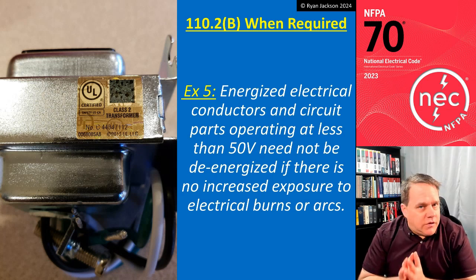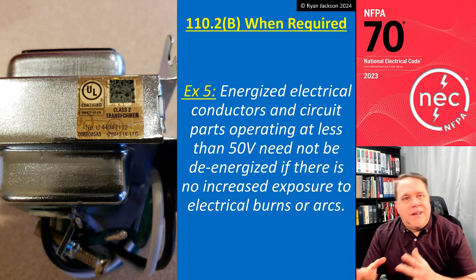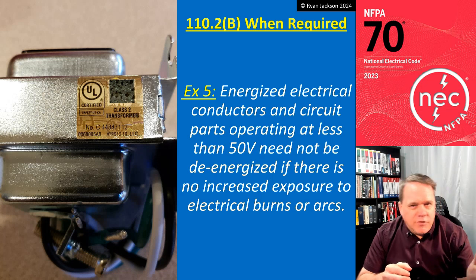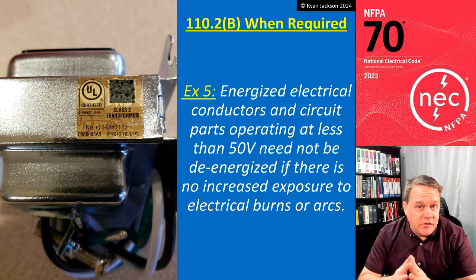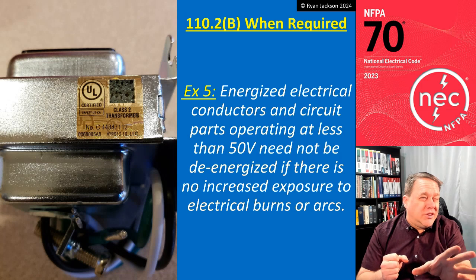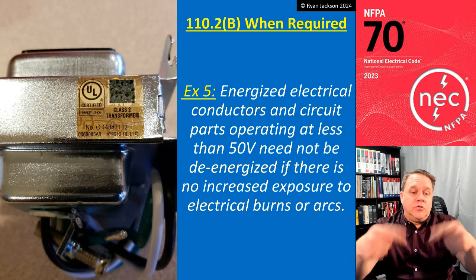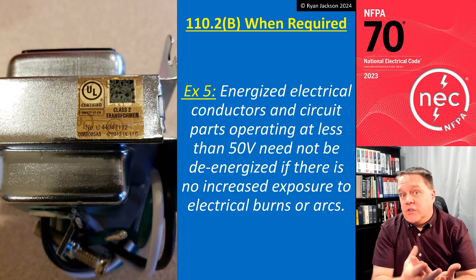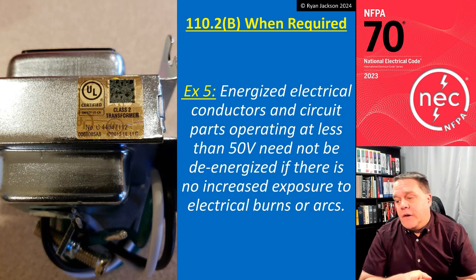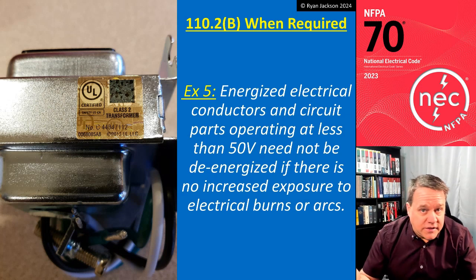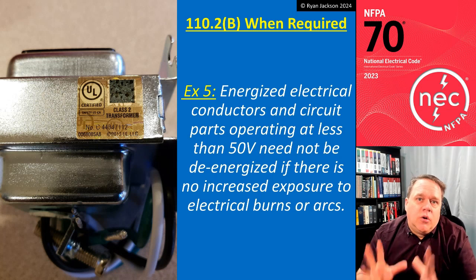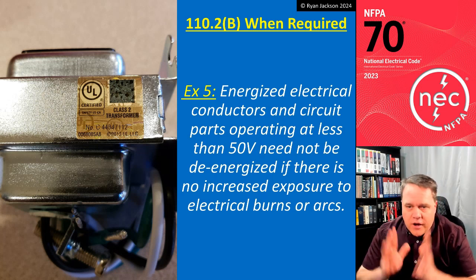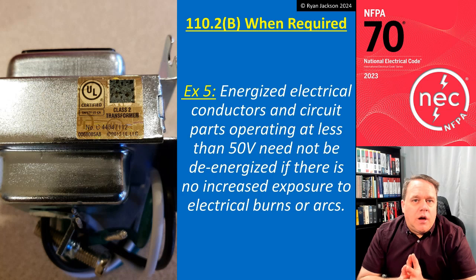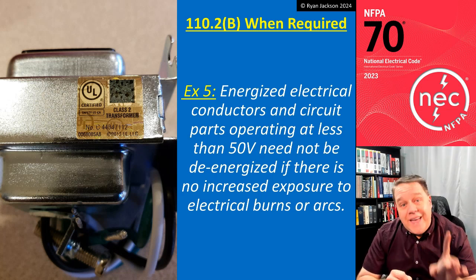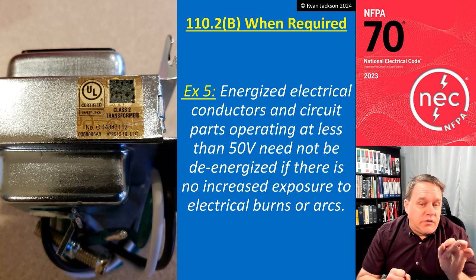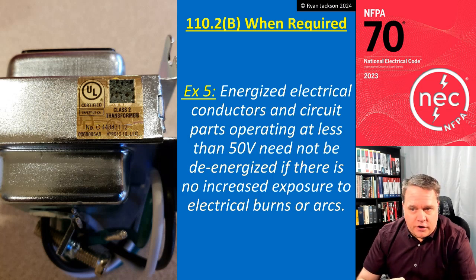But that's not the only hazard. We could potentially have arc flash possibilities at lower than 50 volts. Probably not realistically, because you do need to have enough voltage to sustain an arc, but we could have thermal burns, things like that. So electric shock is not the only hazard. So energized parts do not need to be shut off if it's less than 50 volts and there's no increased exposure to electrical burns or arcs.